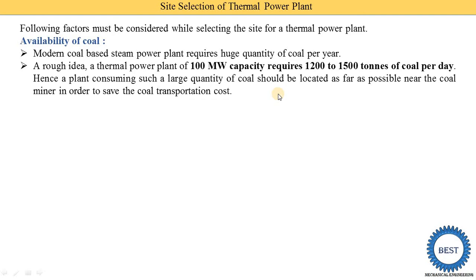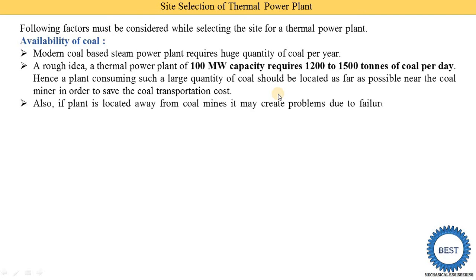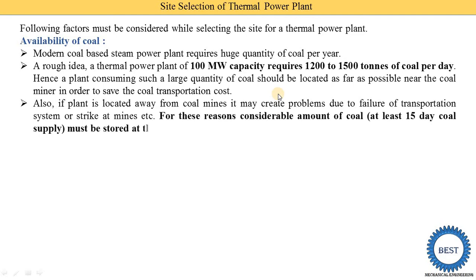It is not always possible to install the thermal power plant near the coal mines, because we also have to consider the load centers, which is also one point for site selection. Also, if the plant is located away from coal mines, it may create problems due to failure of transportation systems or a strike at mines. For these reasons, a considerable amount of coal — at least a 15-day supply — must be stored at the power station.